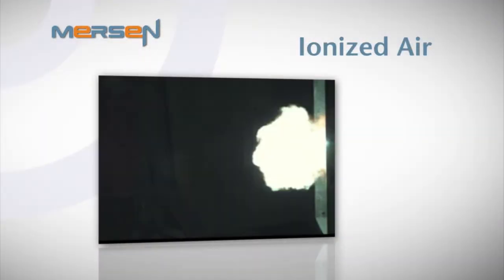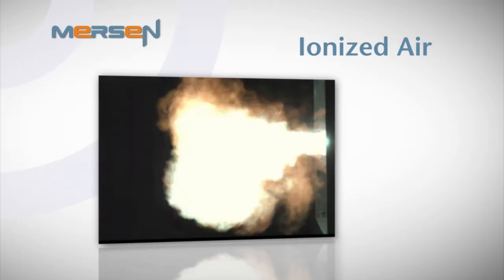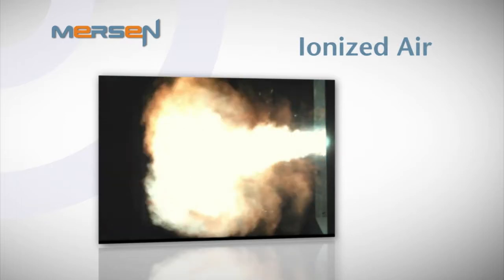The development of a high current arcing fault is essentially like an explosion. When an arcing fault is being established, current begins passing through ionized air. Large volumes of ionized gases, along with metal from the vaporized conductors, are rapidly expelled. As the arc runs its course, electrical energy continues to be converted into extremely hazardous forms of energy. And this all happens in less than 0.2 seconds and generates intense heat, so intense it can cause severe or fatal burns. Molten metal, blinding light causing immediate vision damage, and toxic smoke.